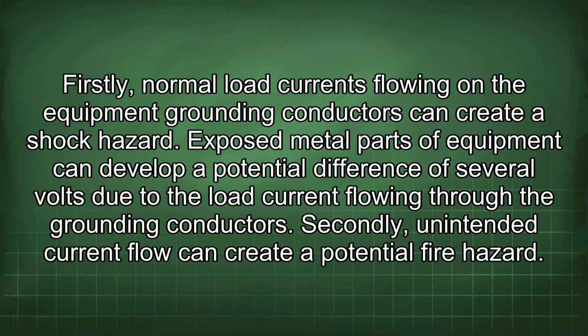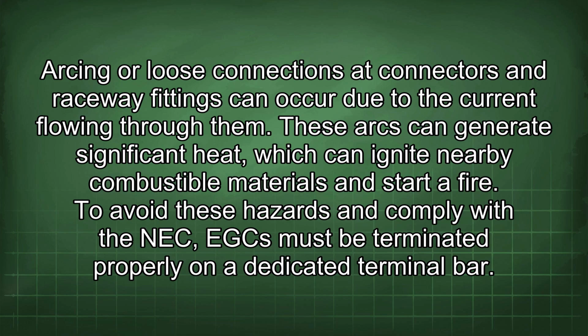Firstly, normal load currents flowing on the equipment grounding conductors can create a shock hazard. Exposed metal parts of equipment can develop a potential difference of several volts due to the load current flowing through the grounding conductors. Secondly, unintended current flow can create a potential fire hazard. Arcing or loose connections at connectors and raceway fittings can occur due to the current flowing through them. These arcs can generate significant heat, which can ignite nearby combustible materials and start a fire.